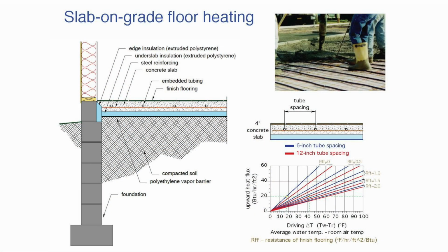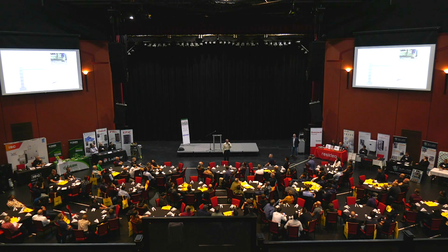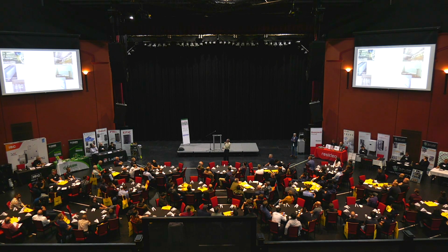And obviously, slab on grade, we can get to low temperatures. We want low resistance floor coverings, and the under slab insulation. Over the years, I think, Robert, you and I have seen the bubble foil, and we've seen other stuff going down. Here's the question: if you don't get under slab insulation right the first time, how hard is it to retrofit? You've got one shot in the life of the building, practically, to do it. Do it right, okay? At least 2 inches of extruded polystyrene, maybe even more if you're going for something like passive house ratings.